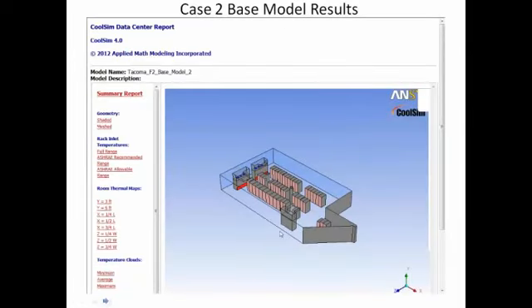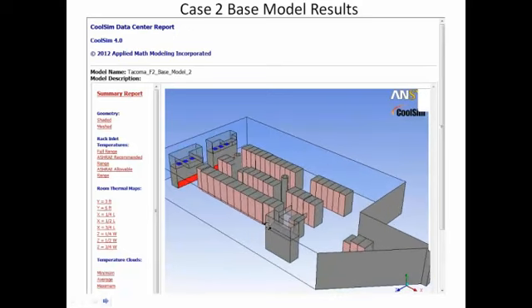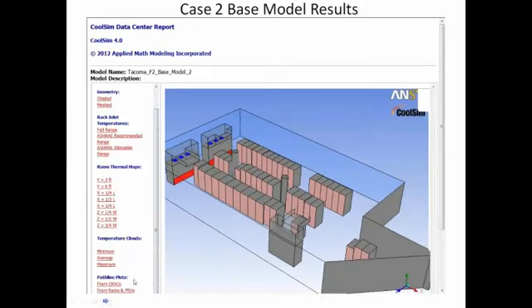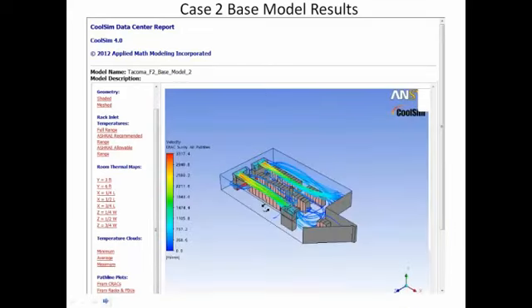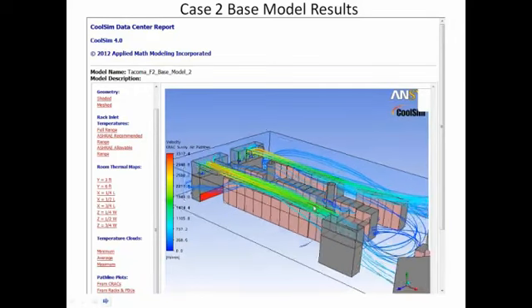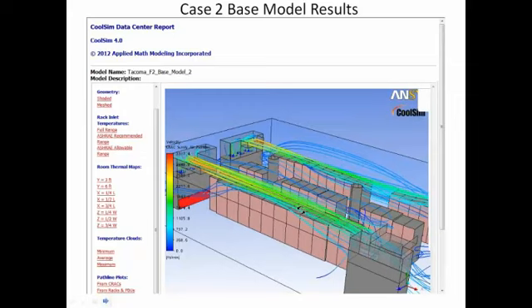So let's take a look. This is a set of results from that, in case you're coming in, and I'll just leave it here for a moment. What I'm going to do is first show the airflow from the cooling units in this case. Magnus, let me know when you can see this, but I've got very high velocity air shooting across the top of that room. Mm-hmm. And the problem you have in these kinds of cases is, again, that high velocity air is shooting across and it's not getting to those units that are close to the CRACs. Again, it's distribution of air. If we had our way, we would dump this air in laminar flow, you know what I mean? We'd let it all come very slowly, in high volume, but very slowly to all of these units concurrently. But, you know, the world is not perfect, and this is what happens.